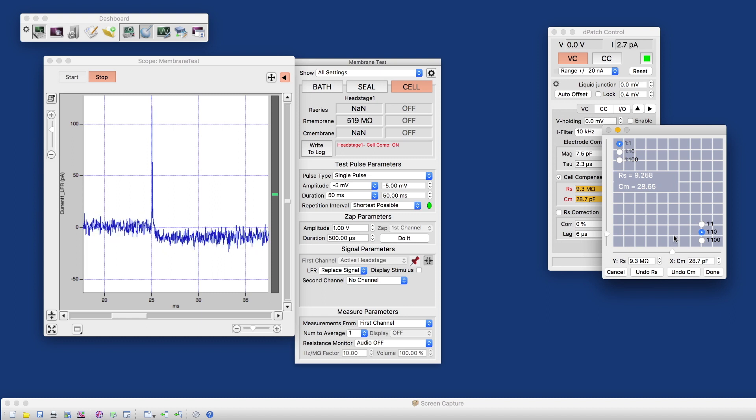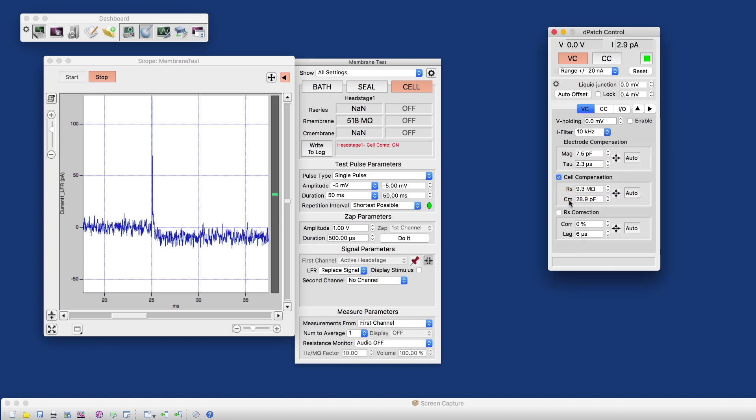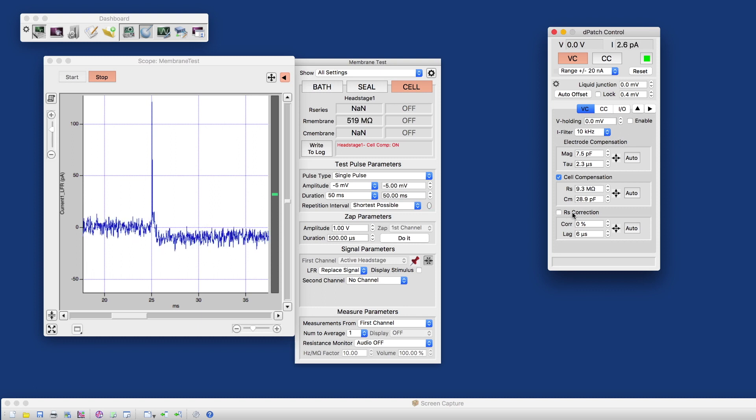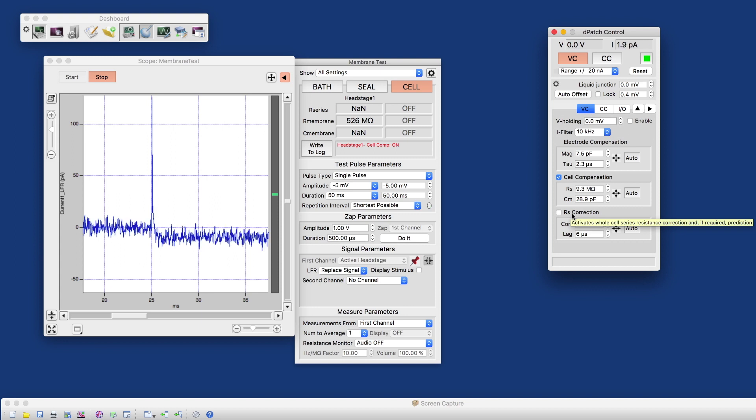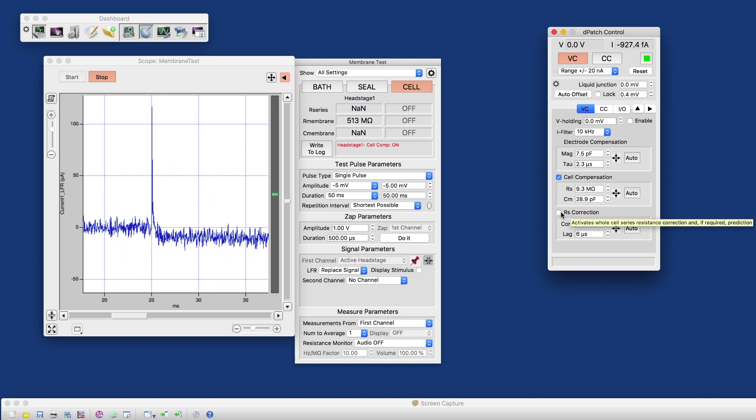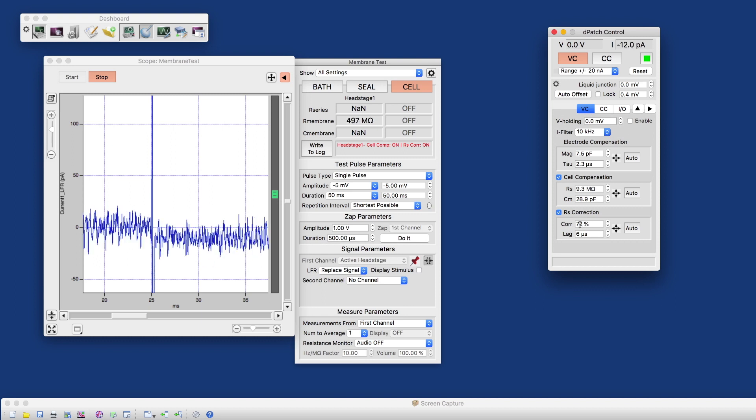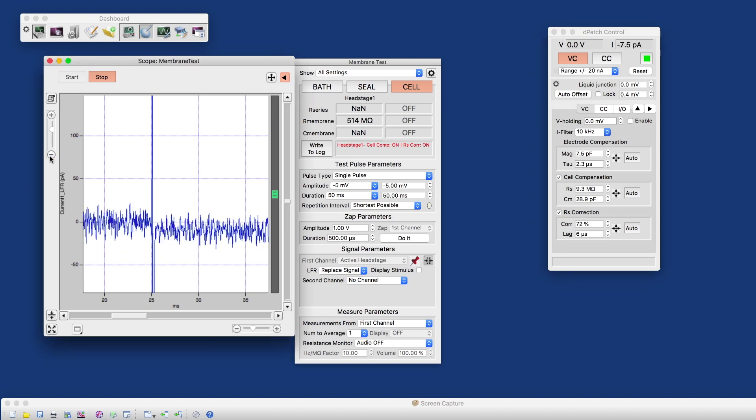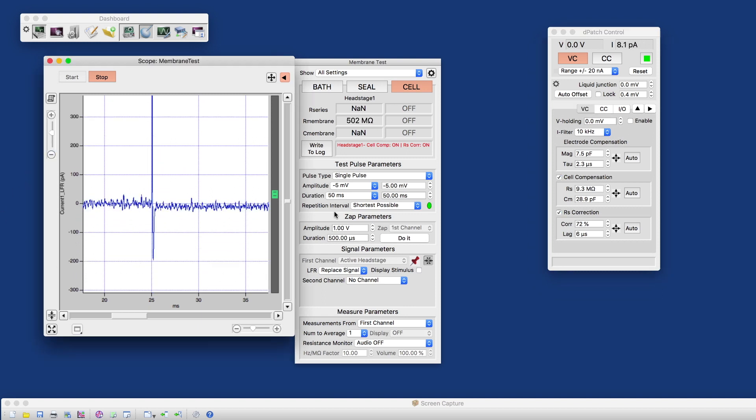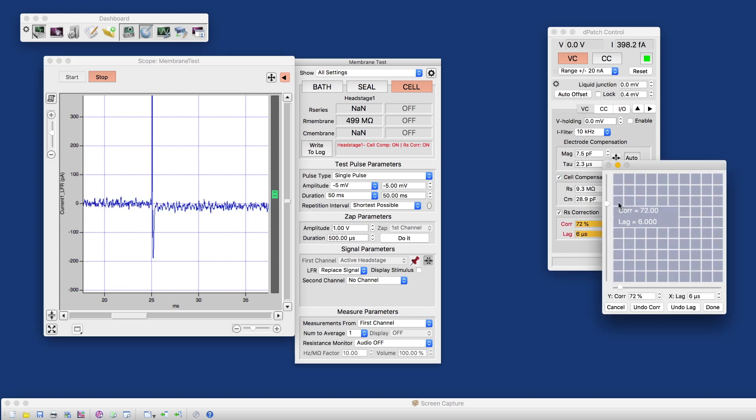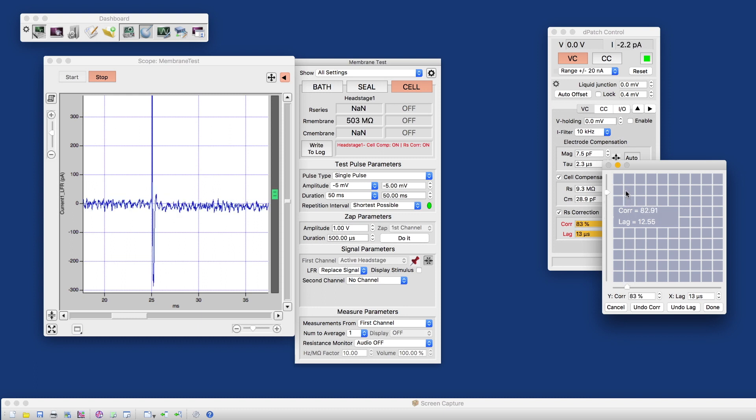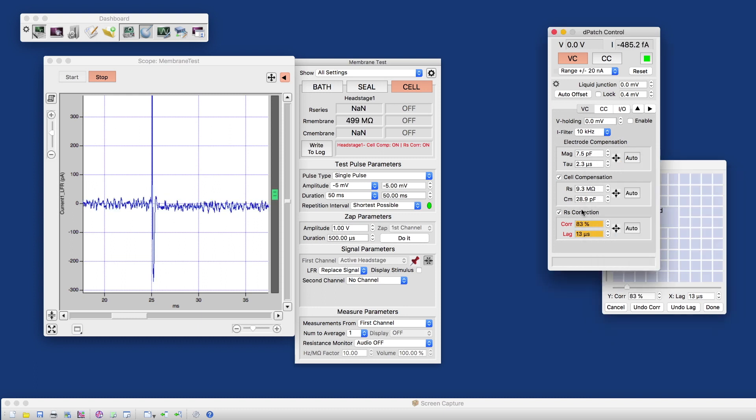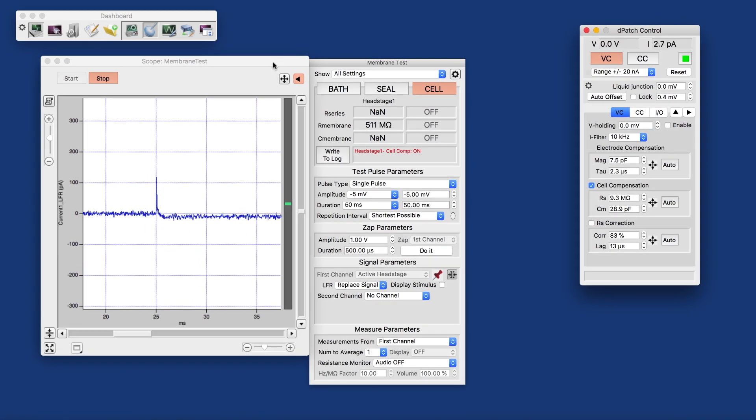I'm not going to spend too much time here on getting that ideal. And the same for the series resistance correction. Due to the digital architecture of the compensation circuits, we can afford to do relatively much series resistance correction, up to 90% should be feasible. But as I said, I'm not going to spend too much time here on trying to optimize that. But we'll just leave it as is and move on to routine data acquisition.